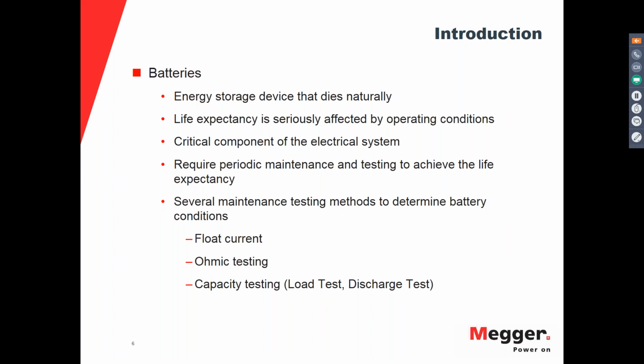Standards and industry practices have several maintenance testing methods to determine the condition of the battery and to determine if the specifications of the battery are being met, or if the quality of the batteries is really what we purchased, or to determine if the maintenance practices are being effective. Several of these methods are listed here. The float current, which is probably not the best way to do it, but it's one of the methods that is followed. Then you also have ohmic testing, which is a very good method and allows you to do the test anytime without any effect on the battery and provides you very good trending data.